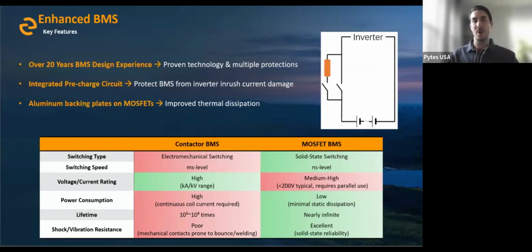Sometimes, depending on the inverter model, when that inverter turns on for the first time, the capacitors within it will energize very quickly and can cause a very high amount of current to be pulled out of the battery. If it's high enough, that can cause damage to the BMS or to the MOSFET specifically, because they're not able to respond fast enough. I see that issue more so with transformer-based inverters like a Victron Quattro or a Schneider XW Pro, not so much with your all-in-ones like Solark or Lux Power, but the potential is still there.